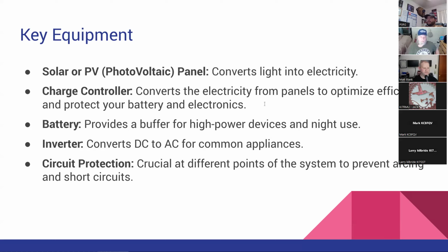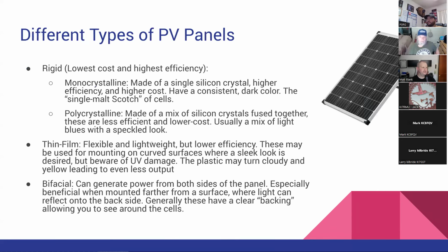You want to have fuses and circuit breakers close to your battery, because the battery is, of course, a huge source of power. Any fault along that, inside the charge controller and the wiring, could cause a short circuit and smoke, which is bad.